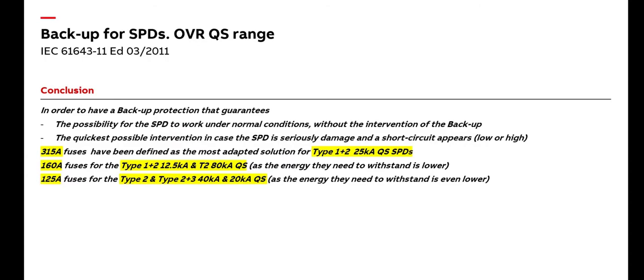So for the fuses, it's clear. All information is in the SPD standard. But for the other devices, basically, it's up to the manufacturer to define all technical details of a correct backup for an SPD. Okay, and in real installation, can we use both fuses and MCB?